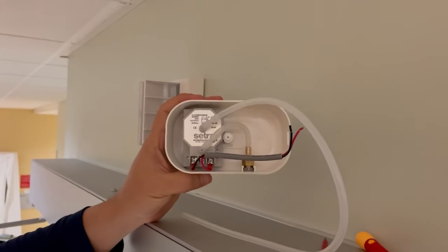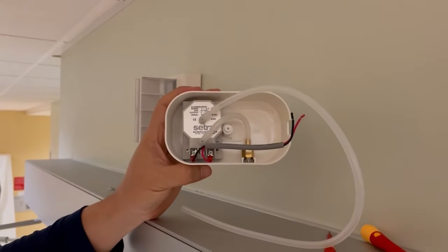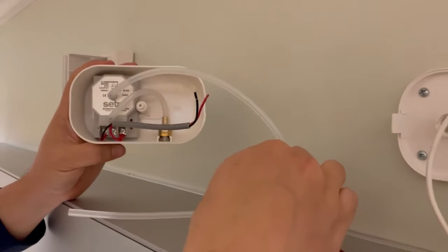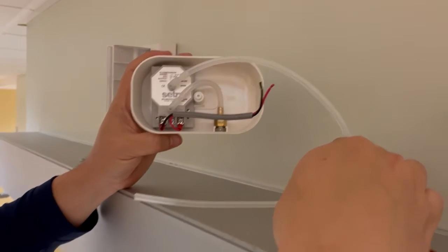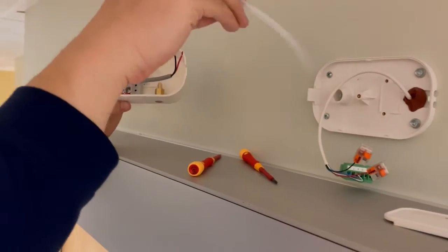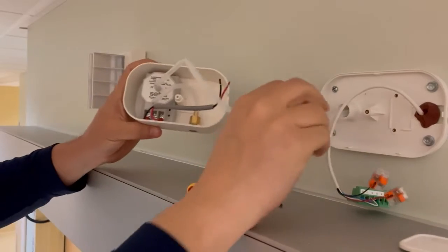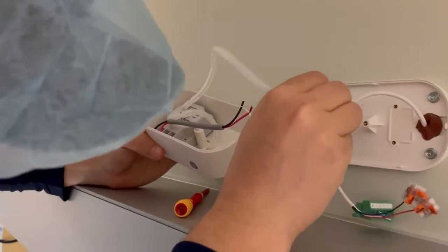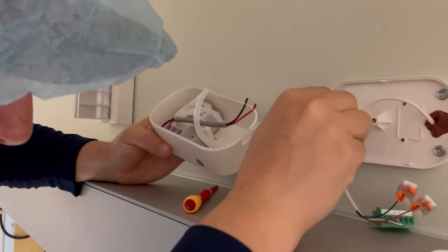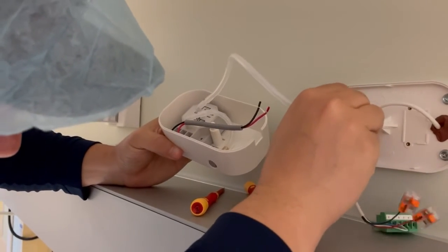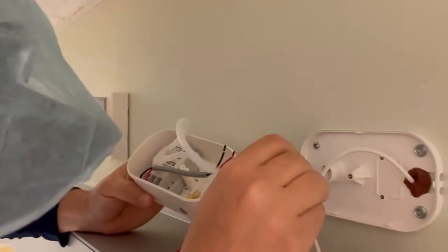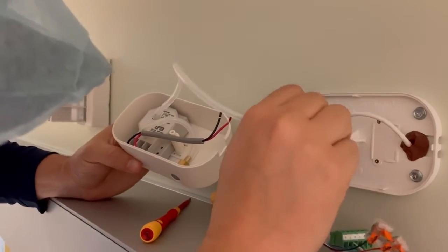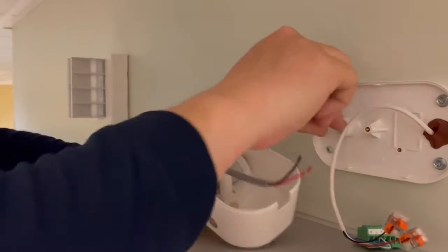Here we're installing the Wago connectors onto the wall wire side. Here we have the Setra cover with the 265 transducer inside. You have pre-stripped black and white connectors for the analog output that will connect to our wall, and a piece of silicone tubing that we will pass through the wall for the pressure pickup inside the room. First pass the pressure tubing through the wall. You do have to get around the hot wire inside the wall, so sometimes the pass through can take a little bit of finesse.